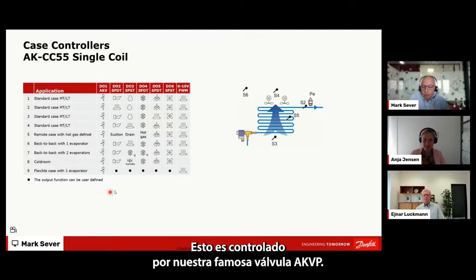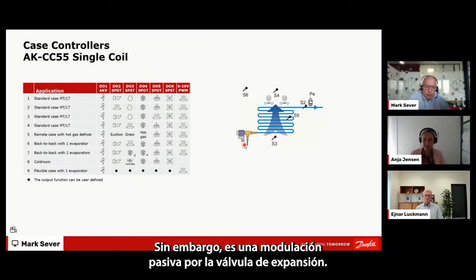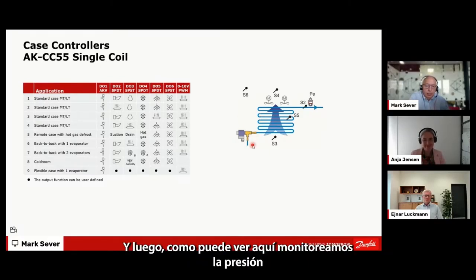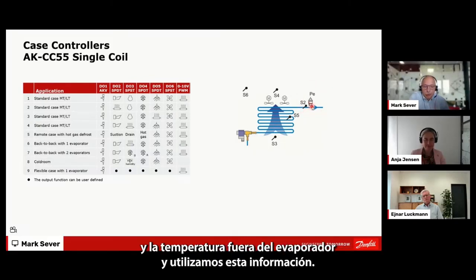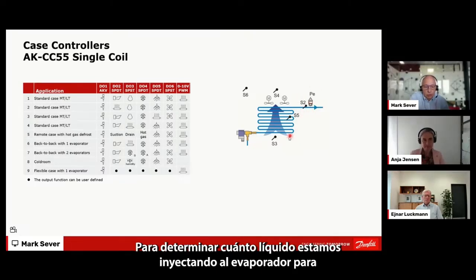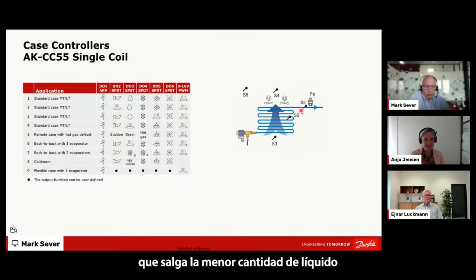It's driven by our famous AKVP valve - it's a pulse width modulation expansion valve. As you can see here, we are monitoring pressure and temperature out of the evaporator, and using this information we control how much liquid we are injecting to the evaporator, to have as low as possible liquid out of it when running adaptive liquid control, which will be mentioned later on.